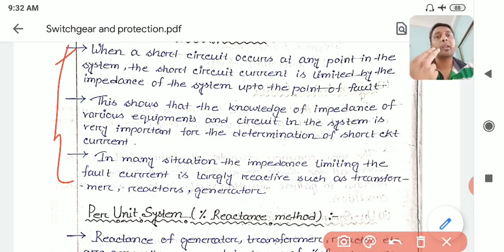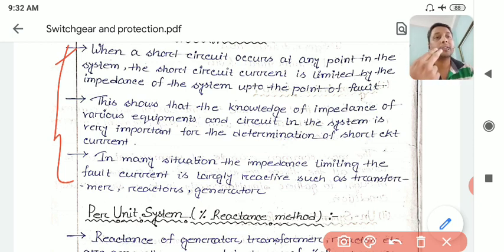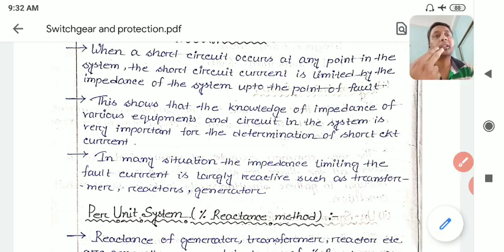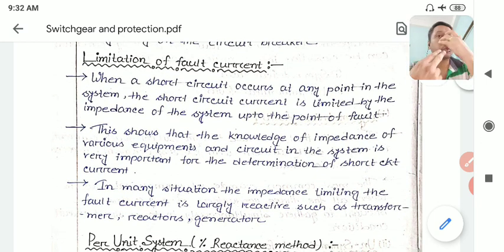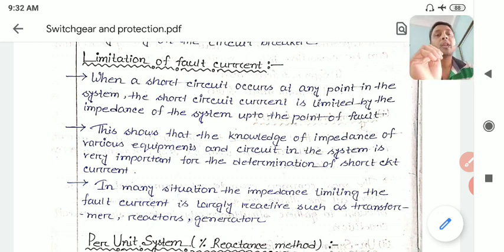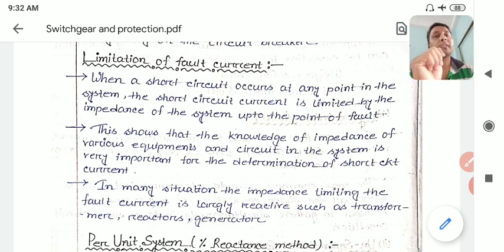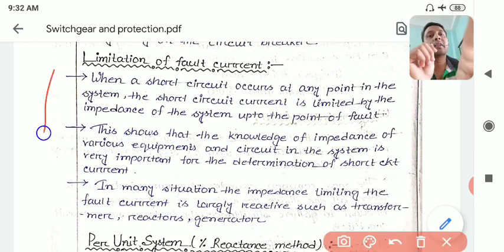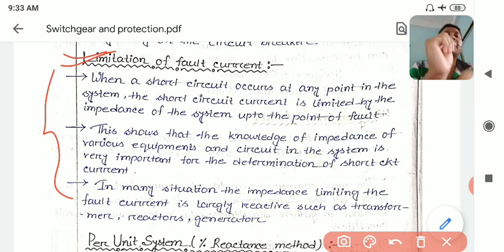As we have studied so far, the fault current always depends on the impedance Zf. Zf is calculated using the Thevenin's impedance, which is the network impedance - generally the generator impedance, then transformer impedance, then transmission line impedance. If the fault occurs at the generator terminal itself, only the generator reactance will come into play. If the reactances are very small, the short circuit fault current will be very high.